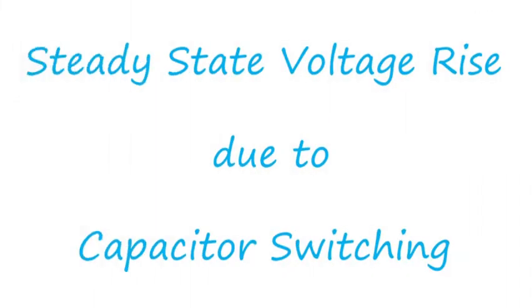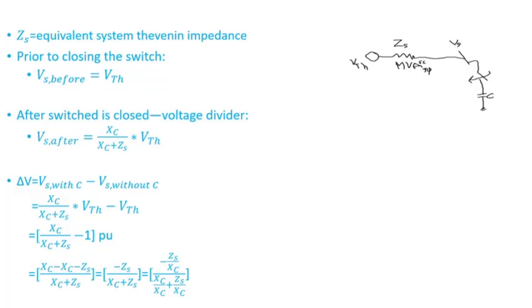Hello and welcome to Engineering Simple. In this video I'll talk about steady-state voltage rise which is caused by capacitor bank switching. At the bus where a capacitor bank is connected, when you switch it into the system there will be a voltage bump or voltage rise, and that can be a problem — it could cause flicker issues. IEEE has some requirements for how much that voltage rise should be: under normal steady-state operation it should not exceed three percent, and under contingency it should be less than five percent.